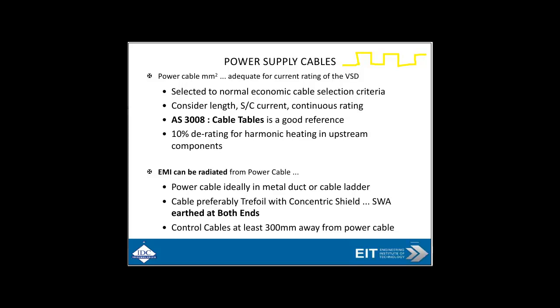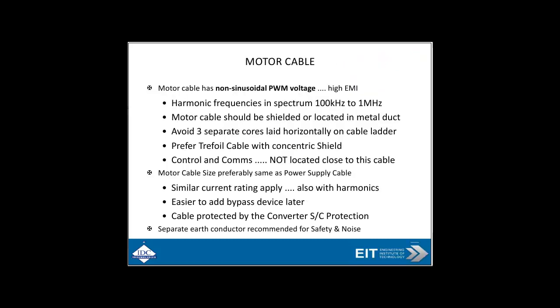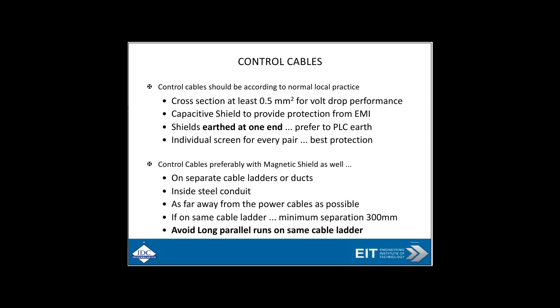For power supply cables, make sure the cross-sectional area in mm² is suitable for the current rating — it's dependent on length, short-circuit current, continuous current rating, applicable cable tables, 10 percent derating, and derating for harmonic heating on non-linear load components. Remember that electromagnetic interference can be radiated from power cables. Control cables should be at least 0.5 mm² for low voltage drop performance, shielded at one end only to the PLC earth, and control cables benefit from a magnetic shield as well.